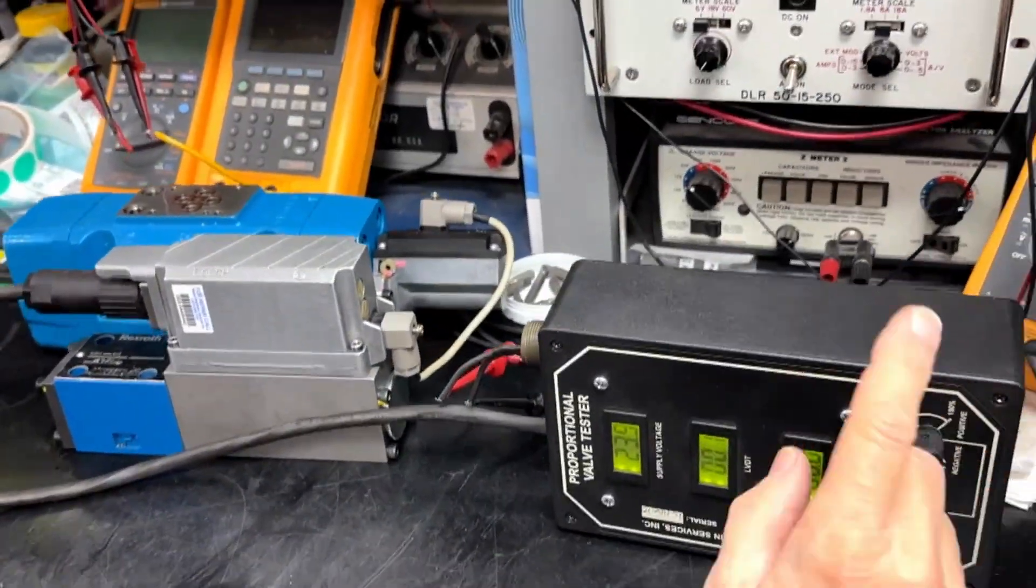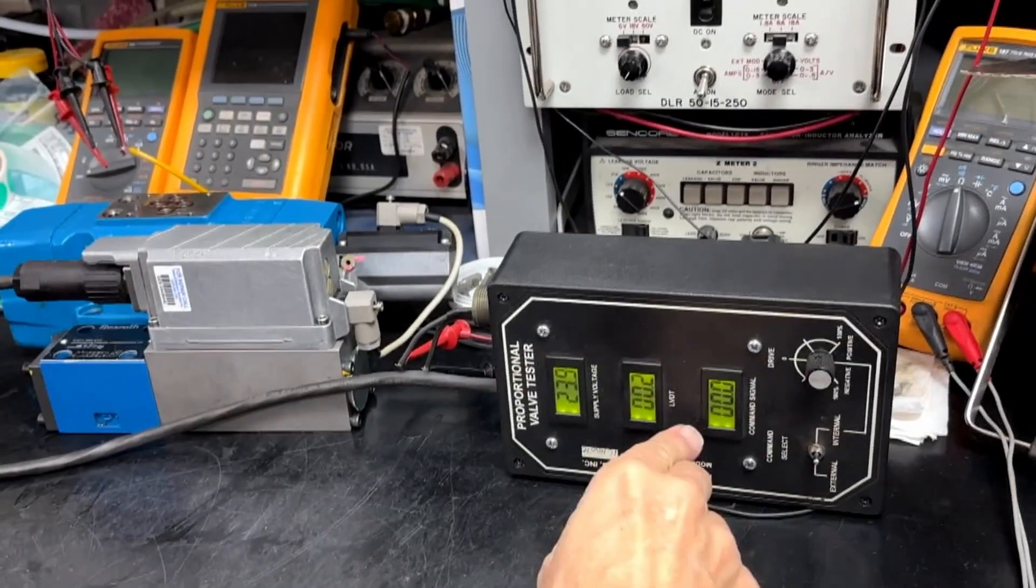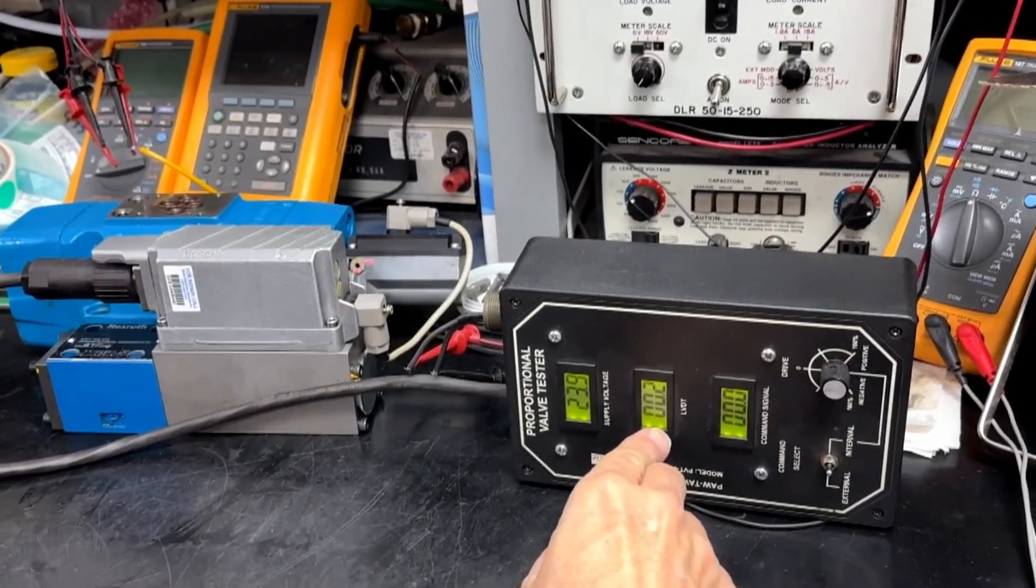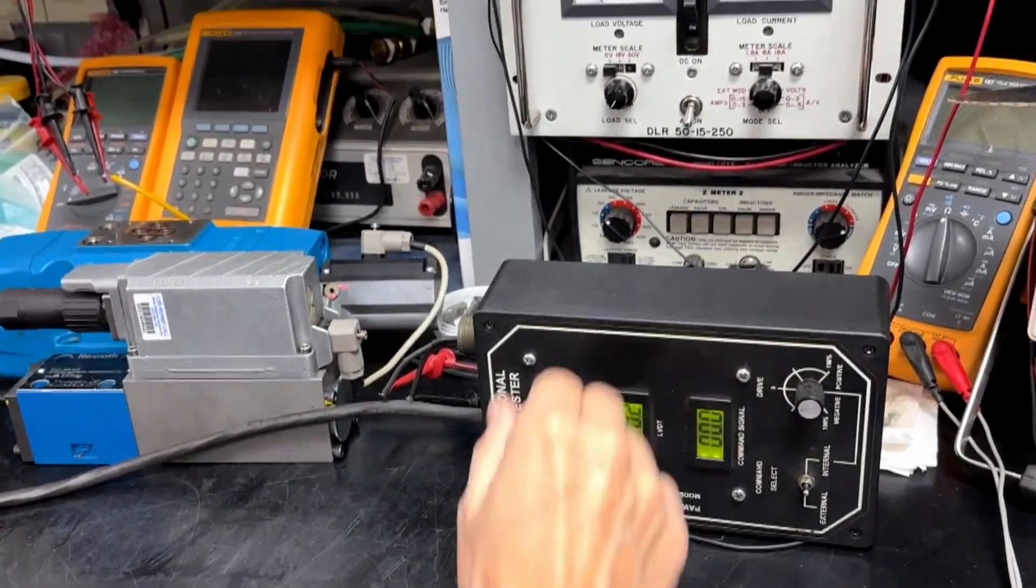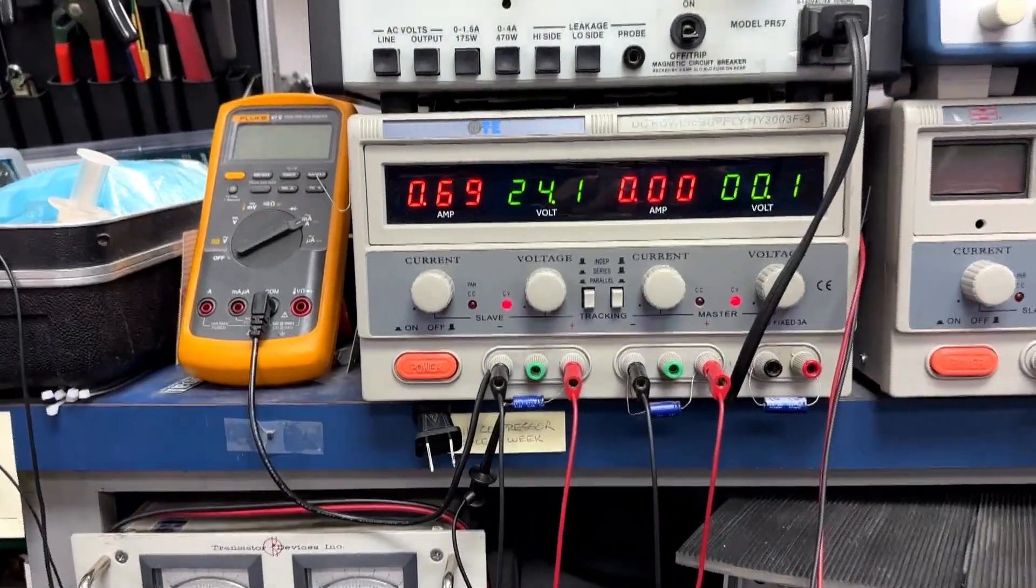To run a test on these, we hook up our valve tester. We have command signal set at zero volts output. This is our feedback section. This is our supply voltage. This is our supply. You can see the current level.